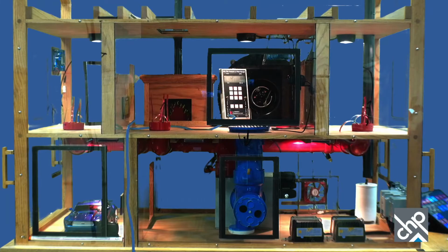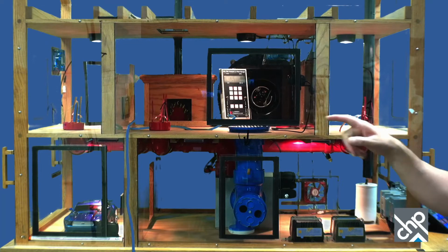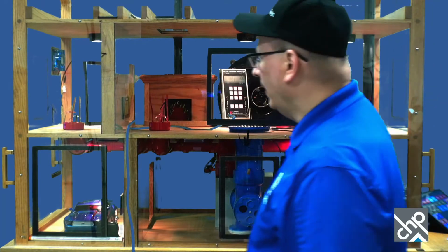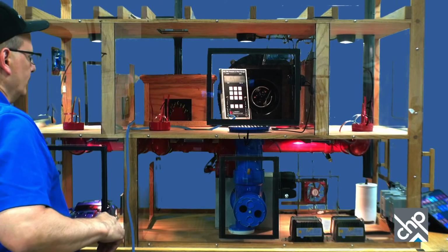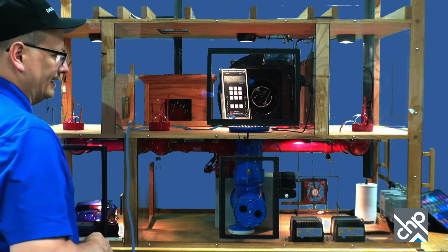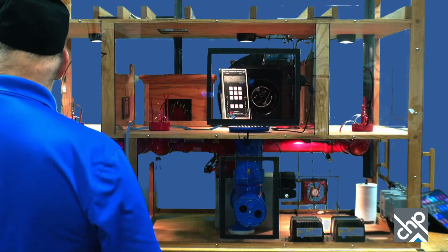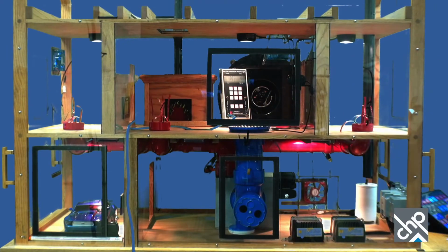You start to get a little bit of a negative number there. So we're like a -1, somewhere around there. So now, that's on the building. Now, let's go back out, and I'm going to close the one to the bathroom over here, and we'll see how it affects things. It's going to be the second door here. And now you can see that we're actually like about a -4 there. So from closing those two doors, now we're at -4.